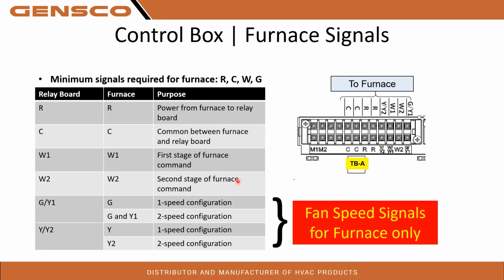Furnace control signals. Pretty much standard stuff. You know, your red is your 24-volt. You're going to wire your furnace into your TBA terminal block. So you will need red for 24-volt, common, your W1s and W2s if you have a two-stage, and your G and your Ys and your Y2 if you have a two-stage. One thing to note, and we'll get into this a little bit more here, is your fan speeds on your Y, Y1, Y2, and G. So the heat pump is going to run off of the G and the Y terminals. It doesn't run off of the W, because the W's will turn on the gas heat.